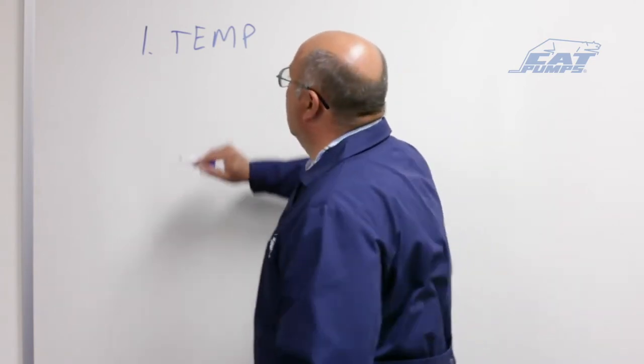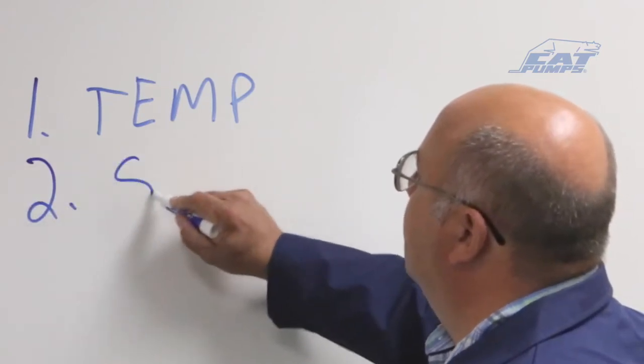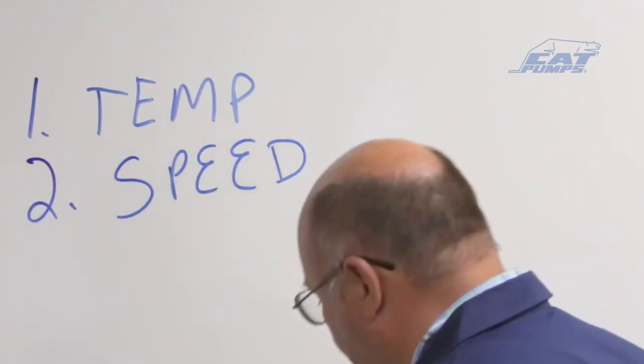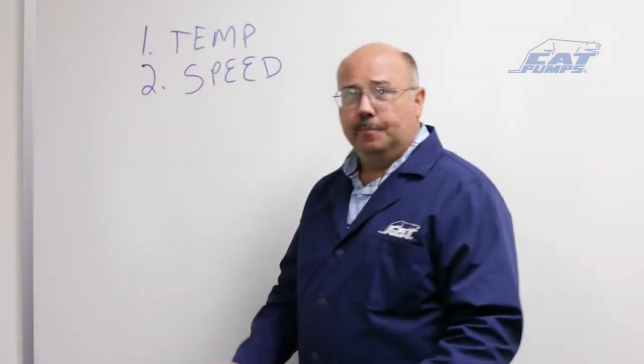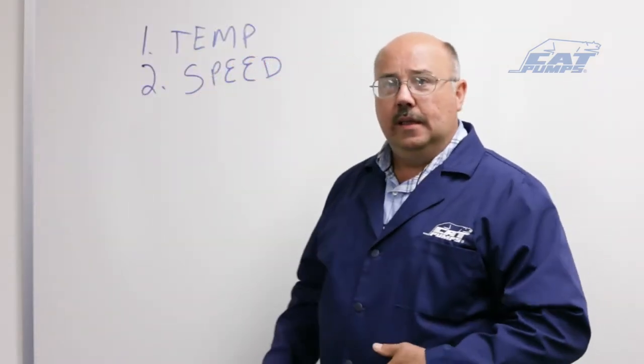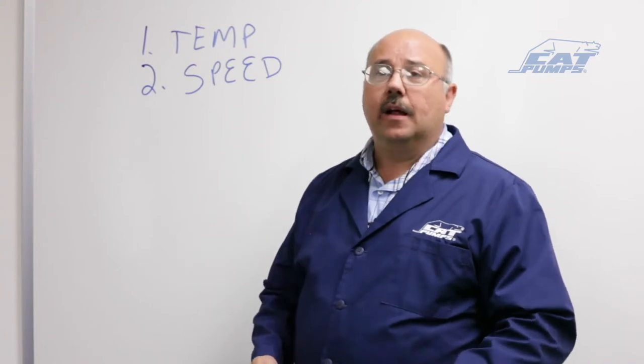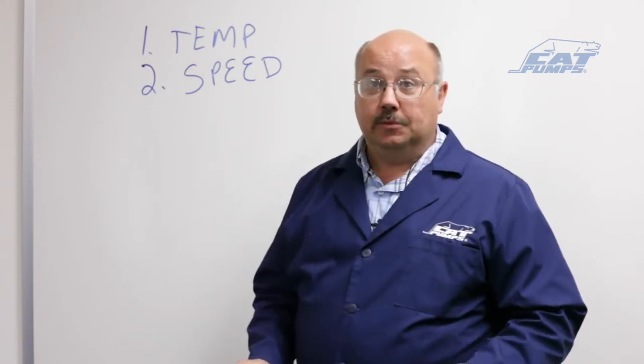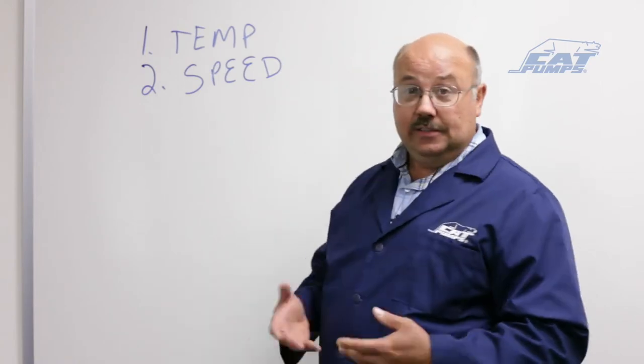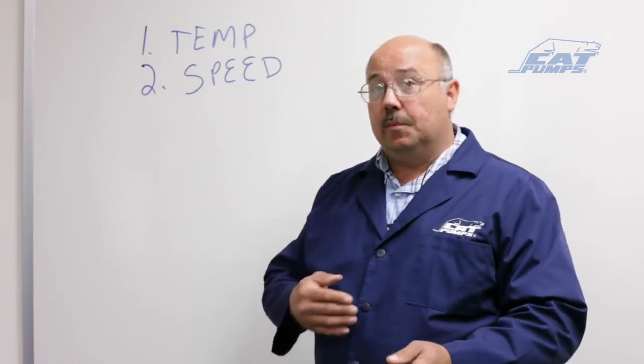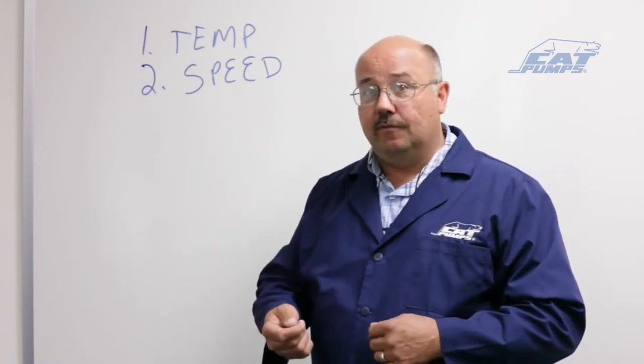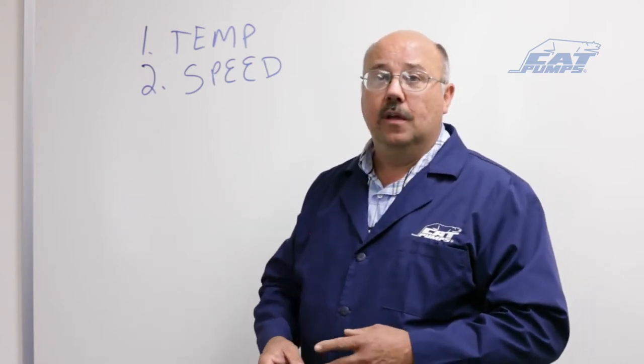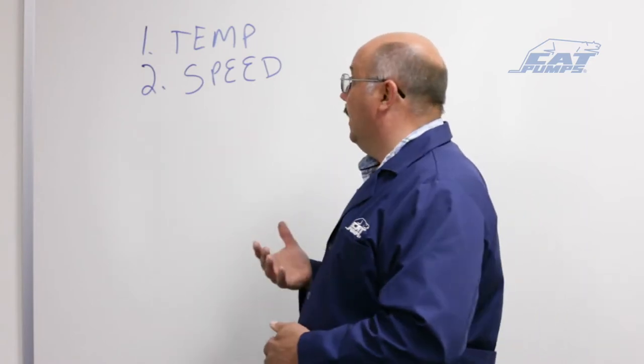The second thing we want to talk about is speed. The speed of the pump will determine how easy we can cause it to cavitate or not. All pumps have a rated maximum speed. If we try to exceed that, then we're going to be moving the plunger faster than it's rated for. And the areas to try to get the water into the valves and the manifold will be exceeded and we could cavitate.